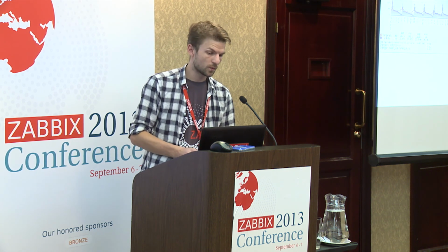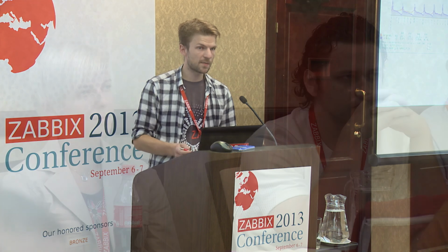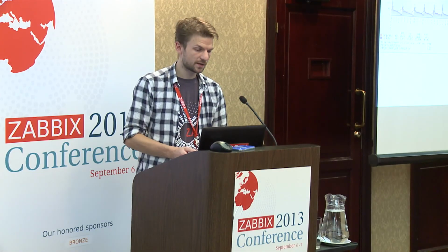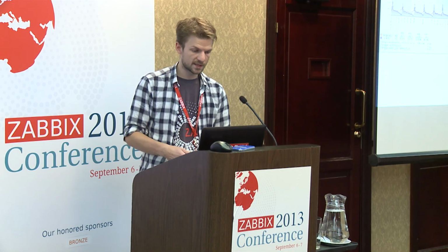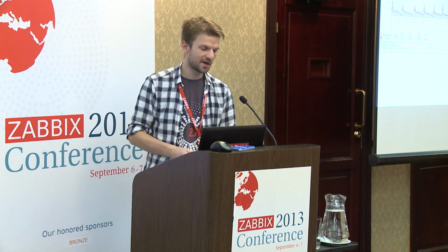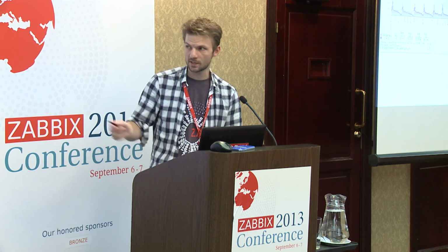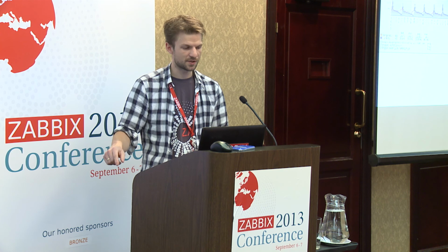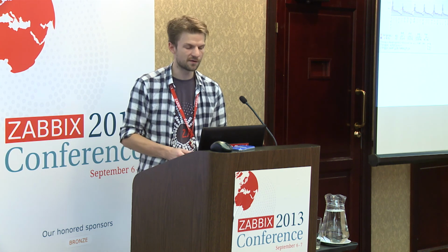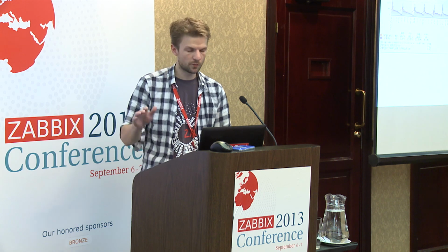And what happened there was the power came back on. It was just a random outage. Nobody turned off the power. It just went away and came back. So the floor-standing air conditioner had to be turned on manually. We got the customer out on the site, turning it back on, and that's when the red line starts to drop again, creating a new baseline with a slightly different threshold. You see it's way higher, but that's because you have to manually adjust below 22 degrees, which is the factory default. But still fine, we're below the threshold.